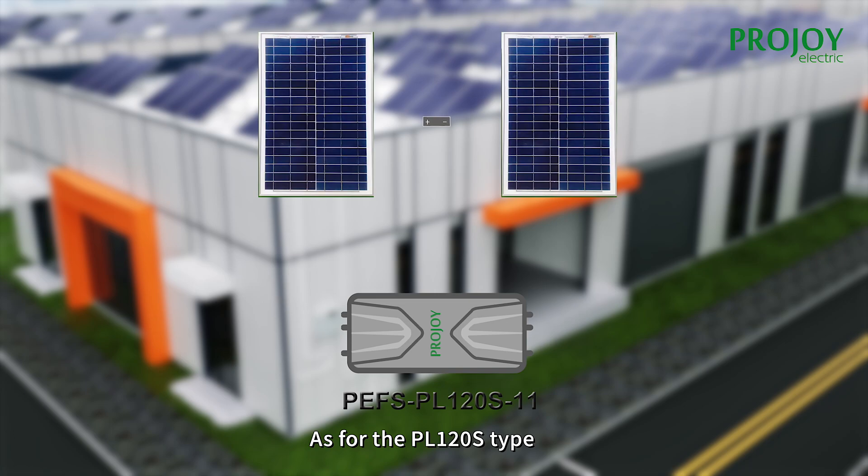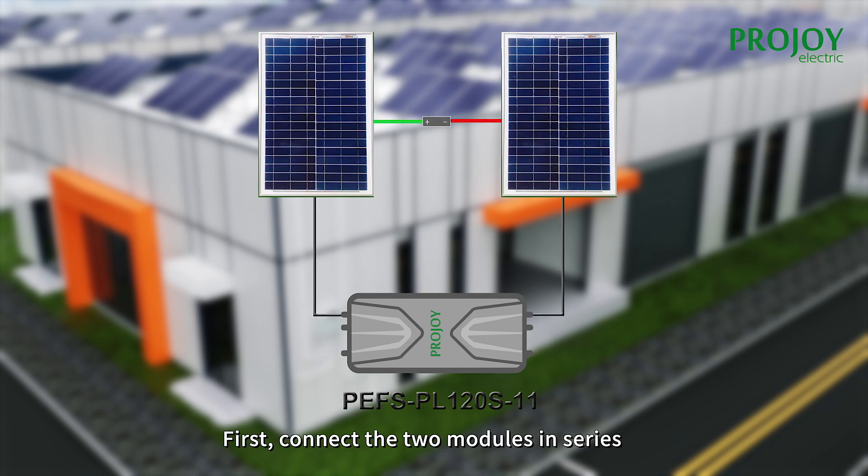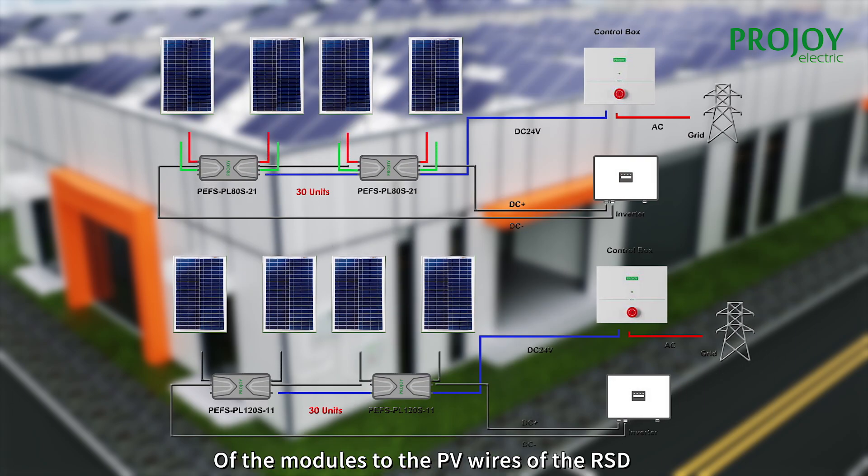Applying the same method to connect the PV2 wire with another module. As for the PL120S type, first connect the two modules in series, and then connect the remaining wires of the modules to the PV wires of the RSD.